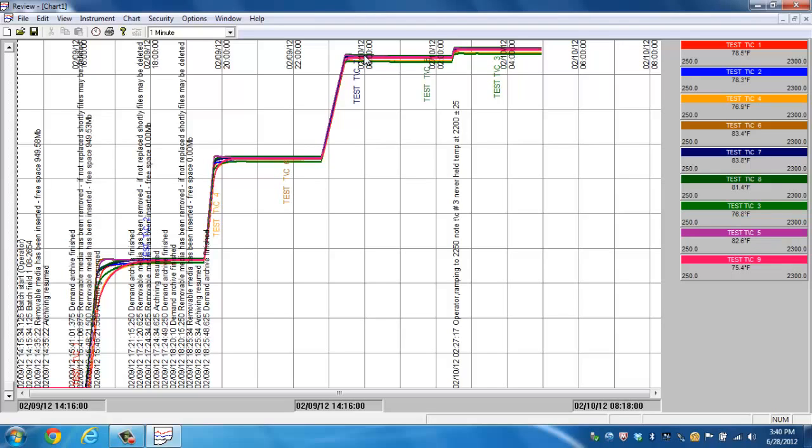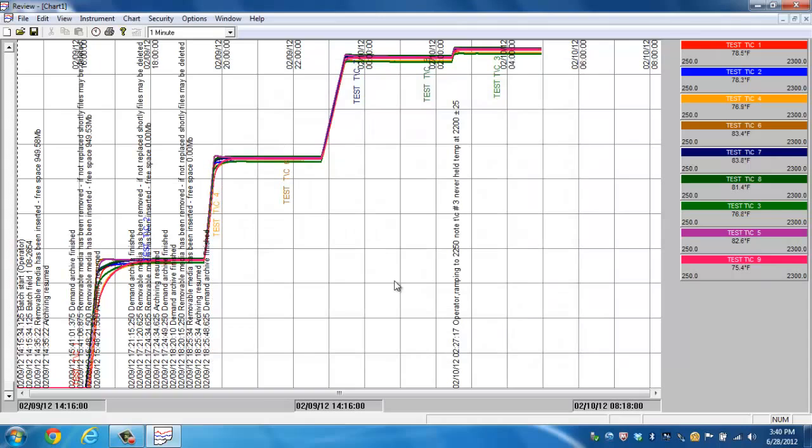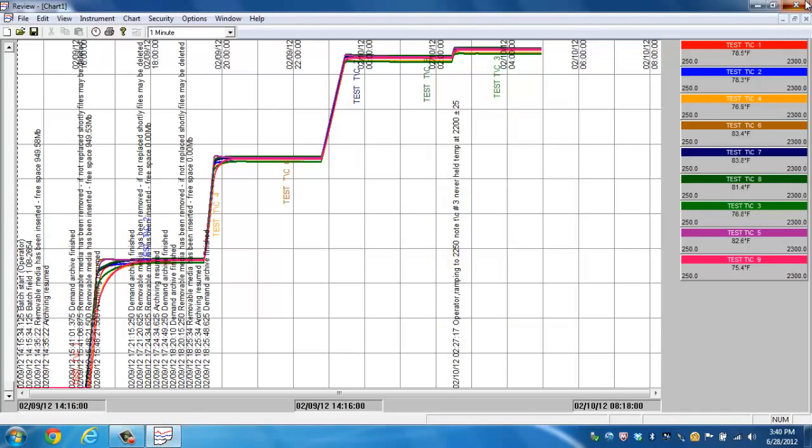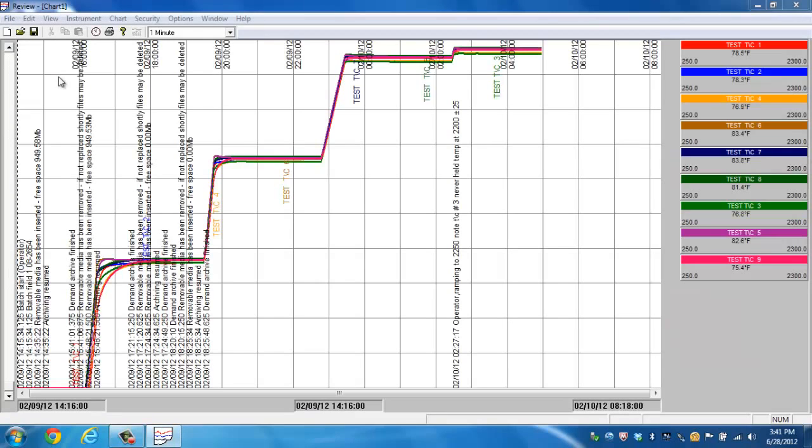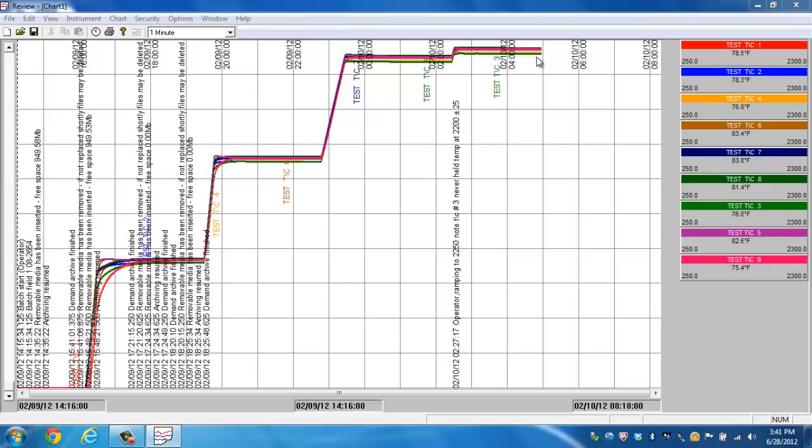From here, you've got a couple of things that you can do. If you wanted to, you can simply go to file and save chart. You can give this a unique name or leave it as default by chart one. If you click that, it will automatically set a chart icon on your desktop. So at a later time, let's say the following day, you close out of your review program. You now no longer have to worry about going into review and having to recreate that chart. All you have to do is click on the chart icon, hit enter, and it recreates that chart for you. Now the benefit about this, however, is if you are connected over TCP IP communications, every time you open up review, review will try to connect to that device and backfill the data. So although it looks like we have no more data after this time, if this was actual up-to-date data, every time we open that chart, it will backfill the following information after that. It will continually keep it up-to-date. Therefore, eliminating the fact that you have to recreate that chart, it's always there. It will always update every time you open up review.